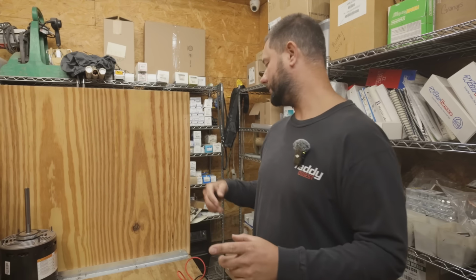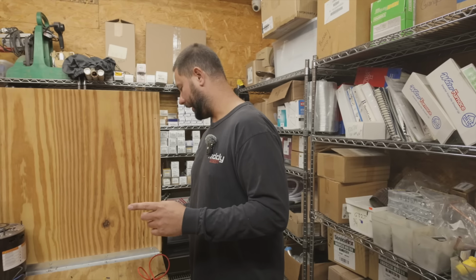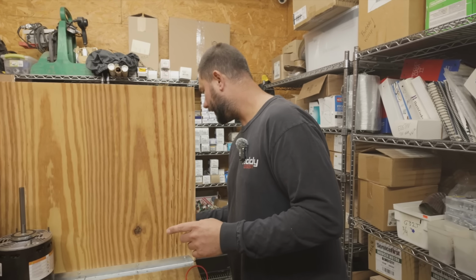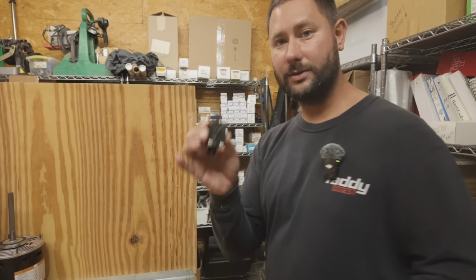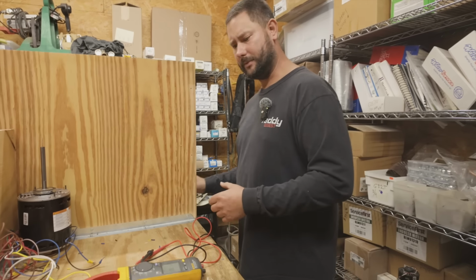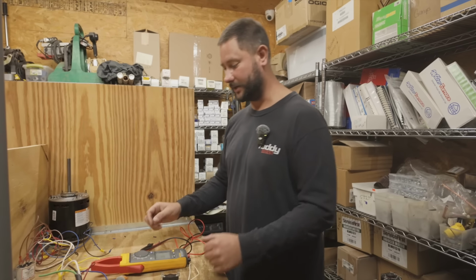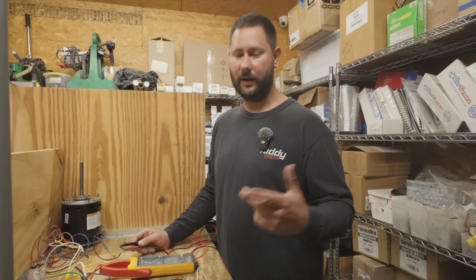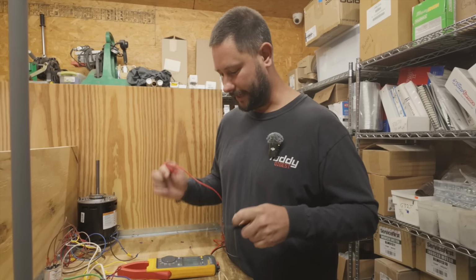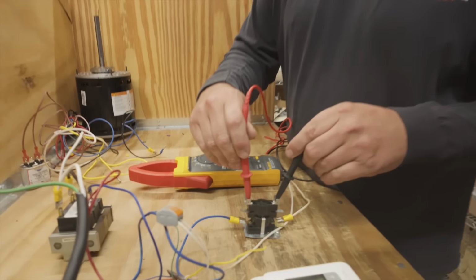And that's the reason that usually you have a relay that looks like this that controls the fan, and then you have a sequencer that controls the heater kit. But sometimes the sequencer controls the fan and heating as well. That way it kicks the fan on when it kicks the heater on. So now, of course, we checked.